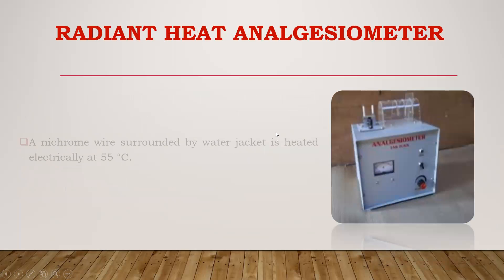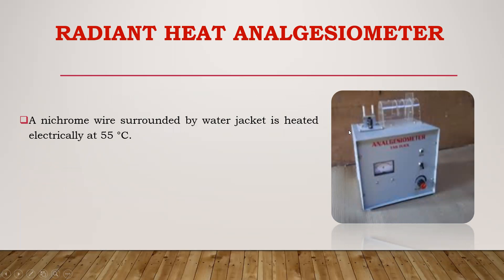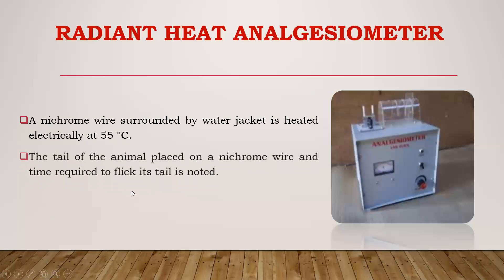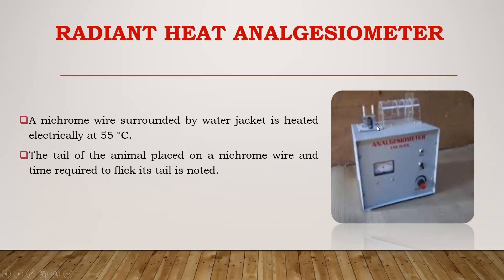The other analgesiometer is the radiant heat analgesiometer. In this instrument, a nichrome wire is provided and this wire is surrounded by a water jacket to prevent heating of the surrounding area. The temperature provided is 55 degrees centigrade. The tail of the rat or mice is placed on the nichrome wire and the time required to flick or remove the tail is noted. The cutoff time for this experiment is also 20 seconds. Separate videos of the actual experiment performance for both analgesiometers are already uploaded on the channel.